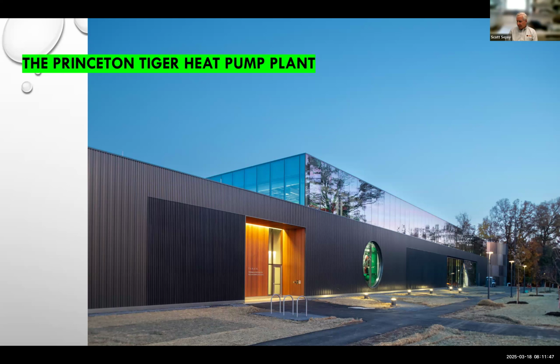We have a new standalone plant, this one tied to our existing cogeneration plant, which gives us redundancy and resilience and allows easier conversion of equipment in our existing plant. When we get the heat pumps at the West plant, until we get those heat pumps running, we make the hot water there with a steam to hot water heat exchanger.